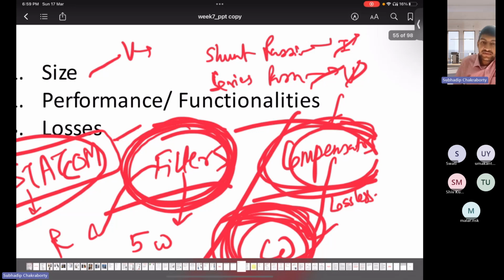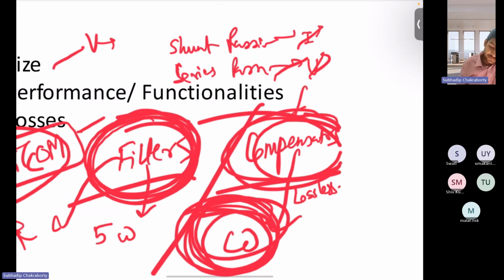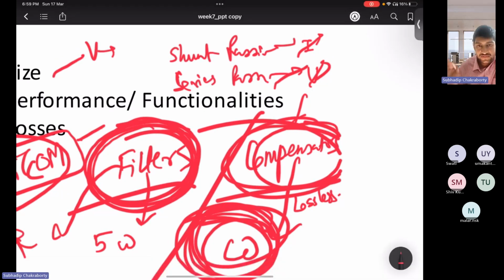Even I told you that when we use DStatCom or some compensating devices, it cannot compensate for the switching frequency harmonics that may appear in the voltage and current. So who will absorb that or filter out that from the grid? So that job is to use the filters, which are responsible for complete elimination of the harmonics from the system. So harmonic elimination is done by the filters, right? Yes. So the filters, what they do, they eliminate the harmonics completely. Okay.